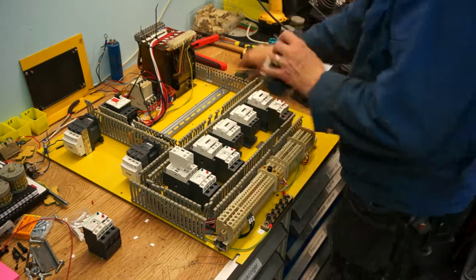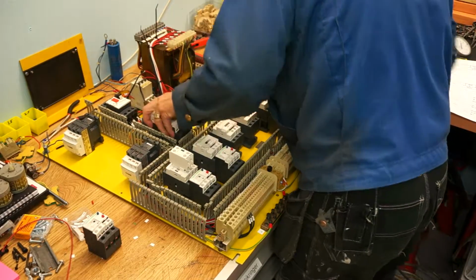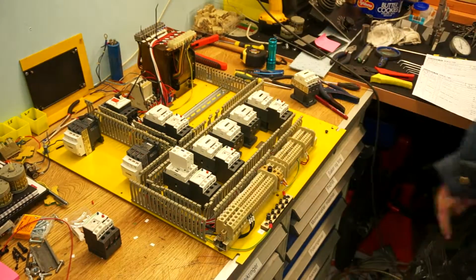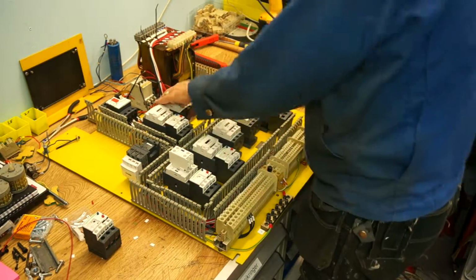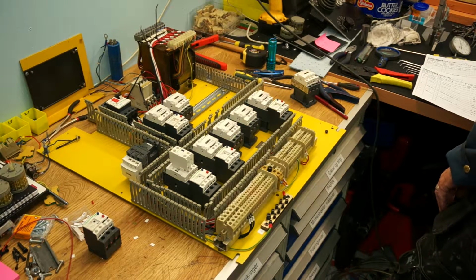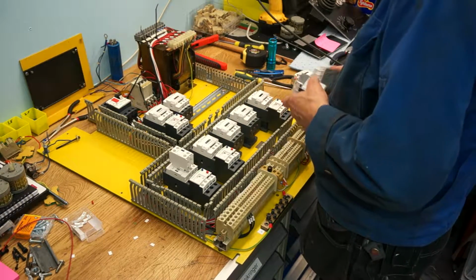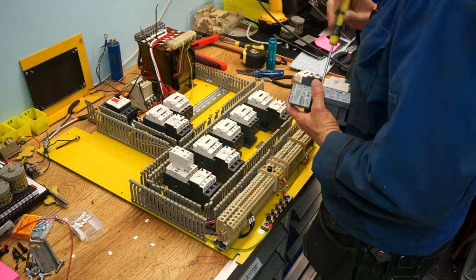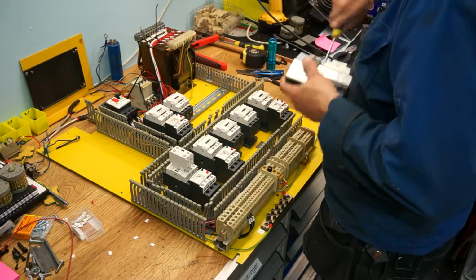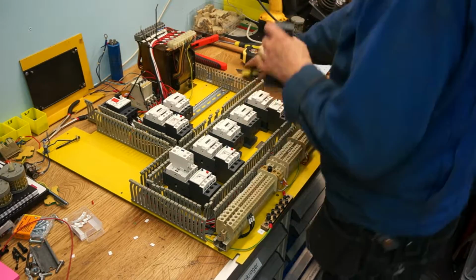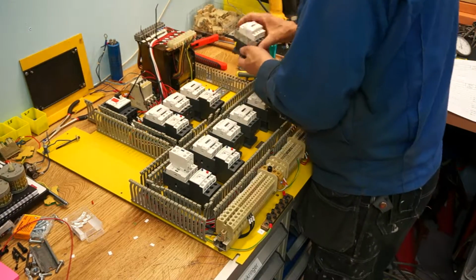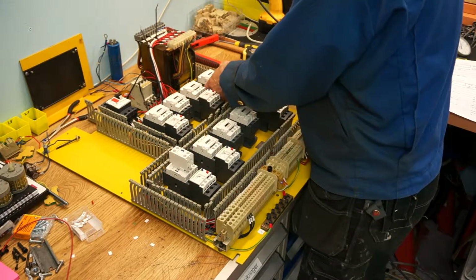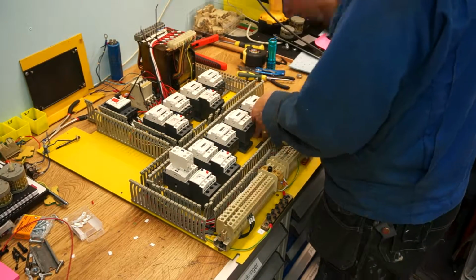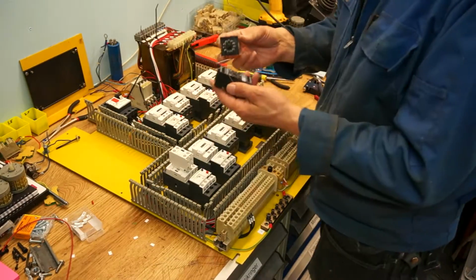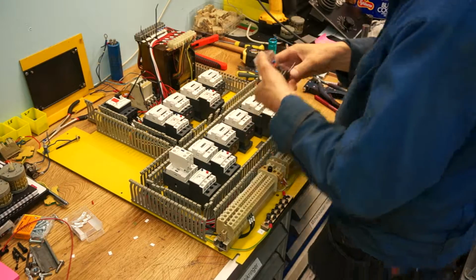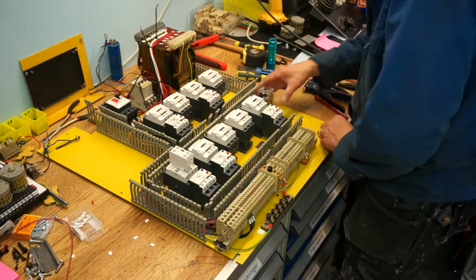I have 9 separate contactors on this mill. 3 of them are for the main motor, for switching between the 2 speeds and the reverse, and there's also one for the motor brake. There's 1 contactor for the coolant pump, and 2 for power feed, which is run by a DC motor, and 2 contactors for the rapid, which is run by an AC motor. So it's 2 separate motors for the rapid and the power feed, and there's an electromagnetic clutch that switches the drivetrain for the table movement between the 2 motors.